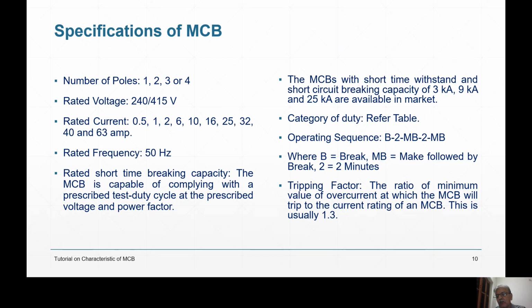And fault current is passing, therefore it will be immediately breaking. Then again wait for 2 minutes and then make-break. So you let the MCB pass through this sequence. Then you take the MCB out and check for operation test, that means whether the MCB is capable of being on, off or not. Then you have to see the temperature rise test. It has to pass the temperature rise test. Then you have to see that it passes the dielectric strength test, that nowhere the insulation has been damaged. If it passes through everything like this, then you can say that it has passed the rated short time breaking capacity test.